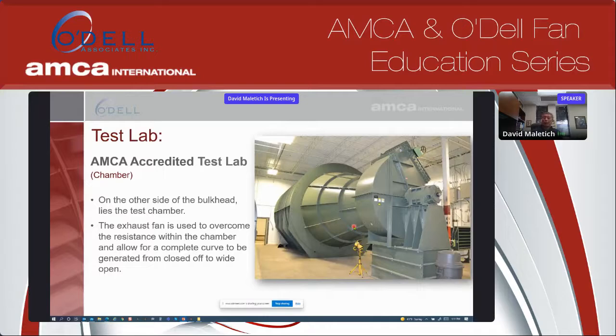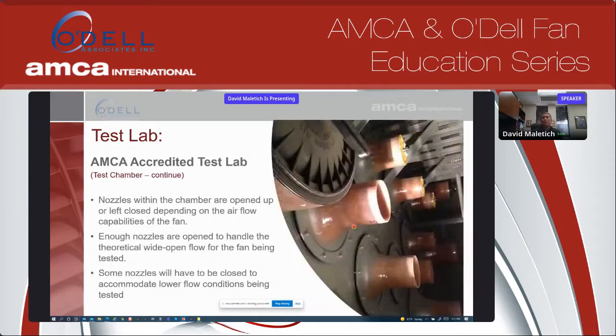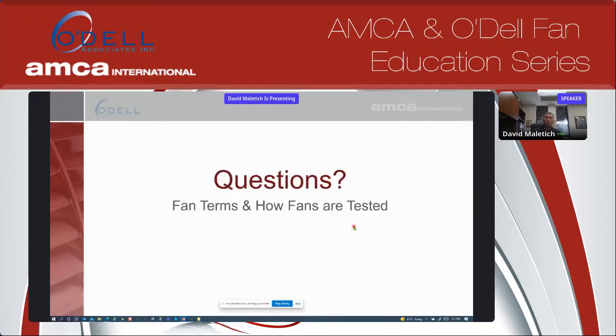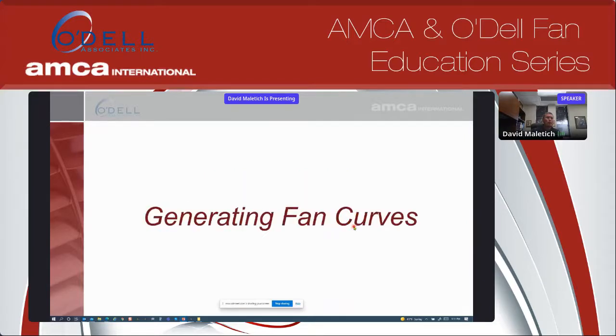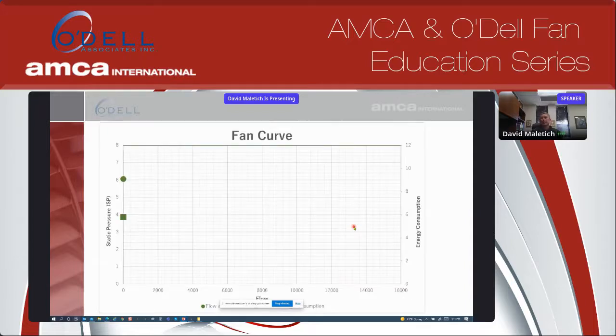Behind the bulkhead is a test chamber, and inside the test chamber is a series of nozzles. By opening and closing these nozzles, we can correlate or change the characteristics of the chamber to match the fan's performance. So if it's a high flow fan, you're going to have more open nozzles. If it's a low flow fan, you're going to have more closed nozzles. Any questions regarding how fans are typically tested and rated at this point? Okay, we'll move on to the next section: how are fan curves generated?